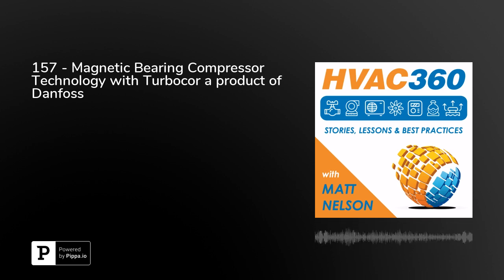Those types of applications include things like air-cooled chillers in hot ambient climates like the Middle East or Phoenix, Arizona, or heat pumps, heat recovery where someone wants very hot water for potable use, ice rinks, and thermal storage. Those are applications where you see that big difference in condensing pressure versus evaporator pressure. The high lift compressor we launched is designed and optimized to handle that high lift application.